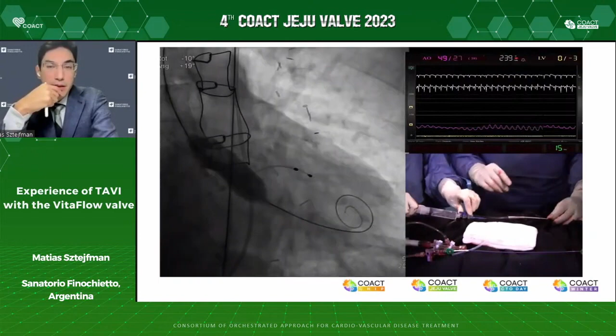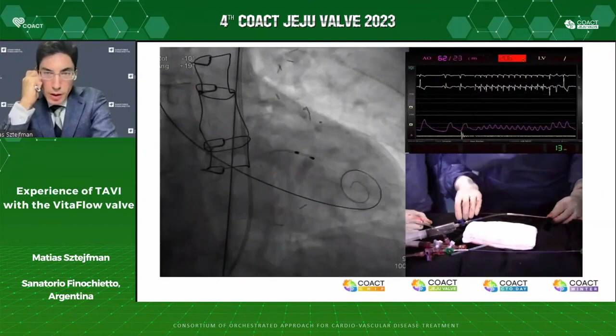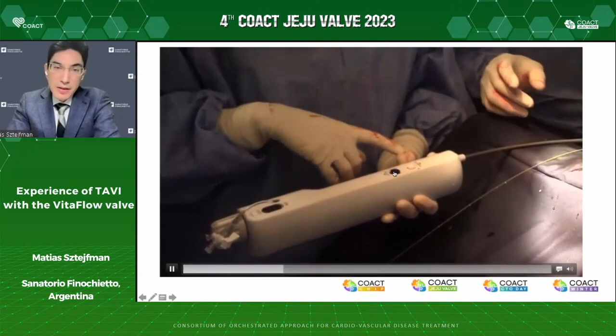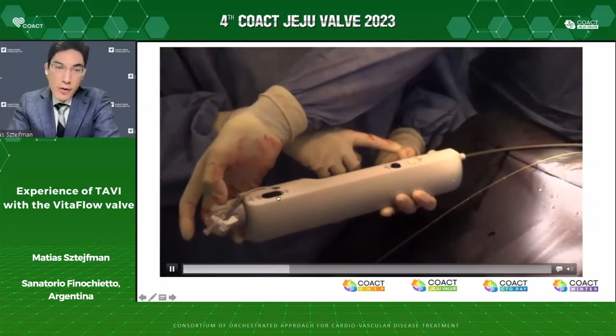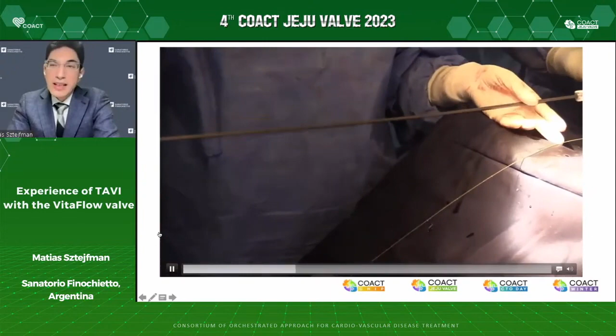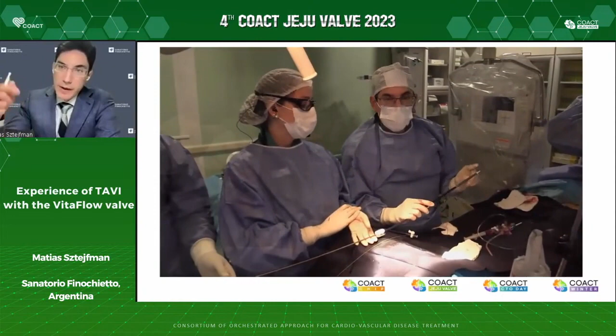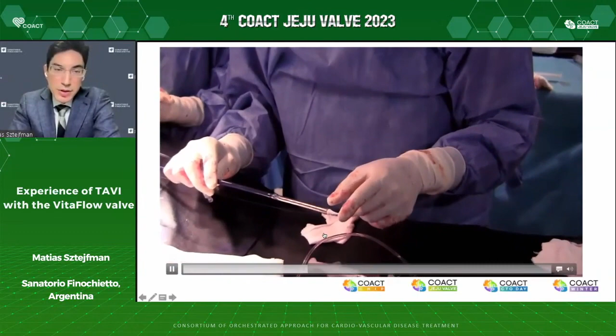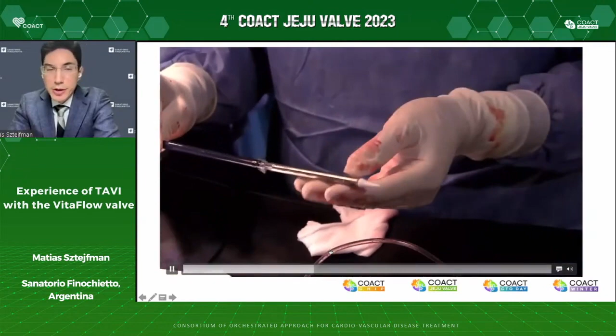using rapid pacing. This is very straightforward BAV. And you are going to see now the delivery system. This is the delivery system of VitaFlow. This blue button is to deliver the valve. Also, you have an on and off button, and this is a manual control in case the battery fails. It has never happened, but if the battery fails, you can deploy the valve manually. And this is the capsule. It's a metal capsule, but the nose cone of the valve is very soft. This is important to avoid any damage to the LVOT and the conduction system. It's very soft.